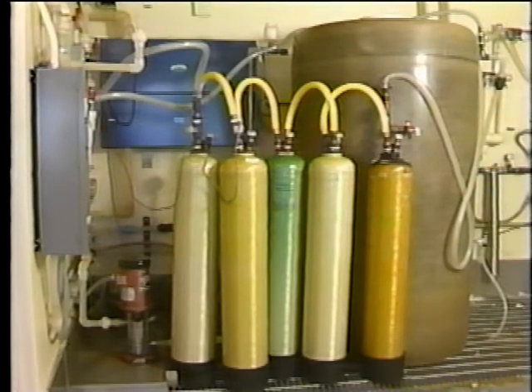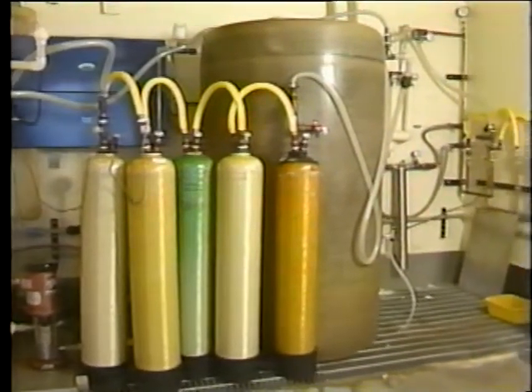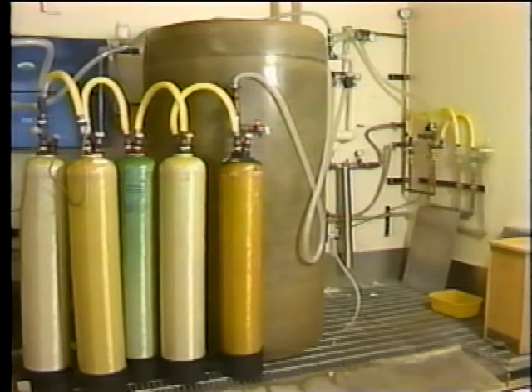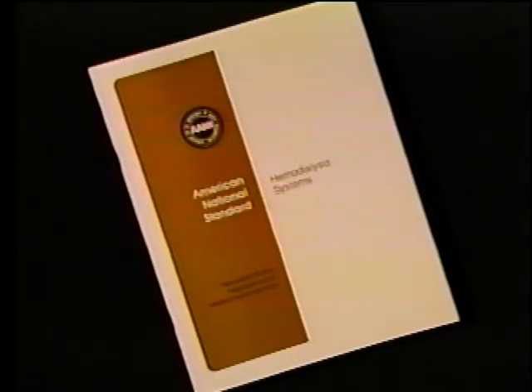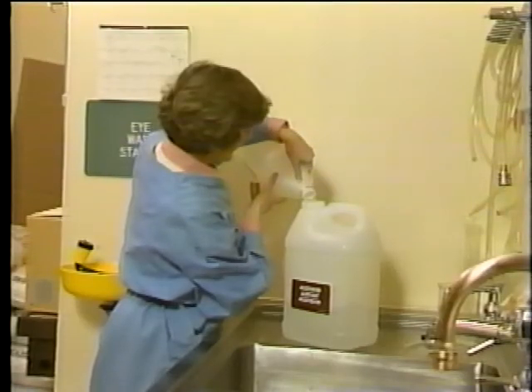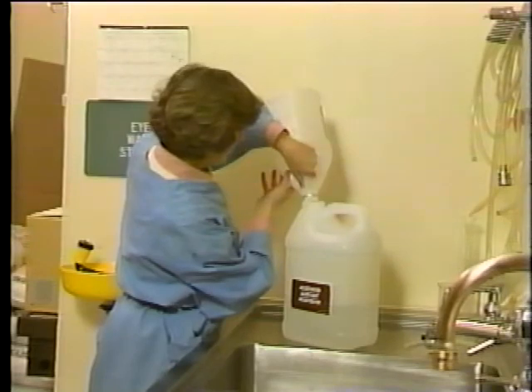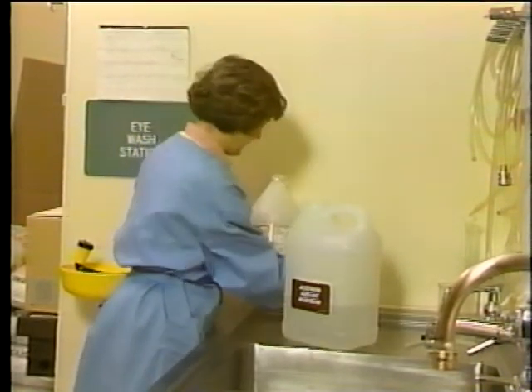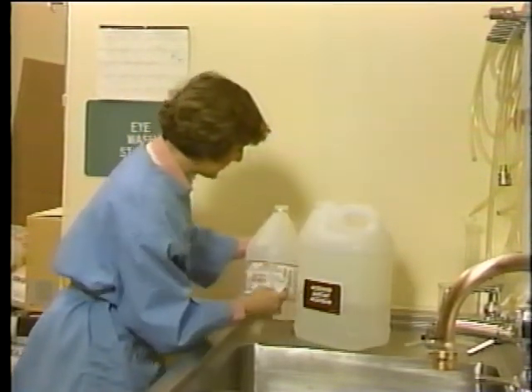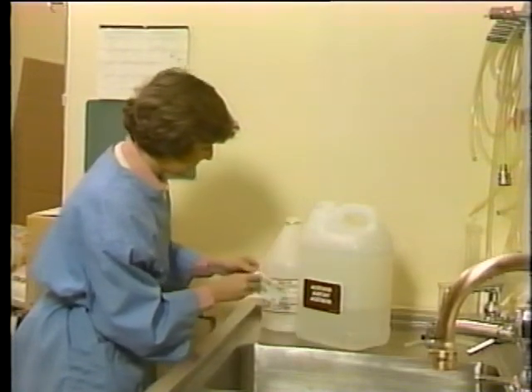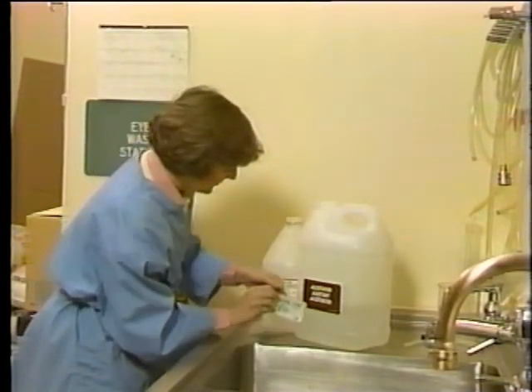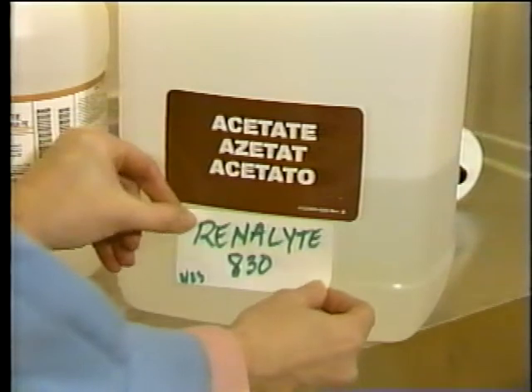Before mixing dialysate solutions, be sure you are using treated water, not tap water. The water should meet the minimum national standard for water quality for hemodialysis systems. Errors can also occur when transferring concentrate from one container to another. Be sure to label all containers properly.